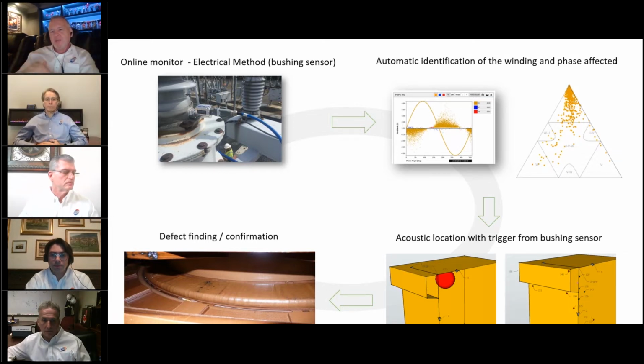Doing it on every transformer is quite an expensive procedure, so our suggestion is really to do this kind of process. You can start with gas on some transformers, using just a simple gas monitor. Then the next step is the permanent electric system, which is cost affordable and at least tells you if there is an issue or not, and in which phase. And then with a portable acoustic system, you go and make the location. So the portable acoustic system in that case is absolutely a good choice, to use when the permanent system raises a hand and says, come on, there's a problem here, come and have a look.